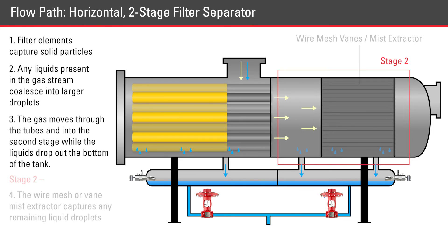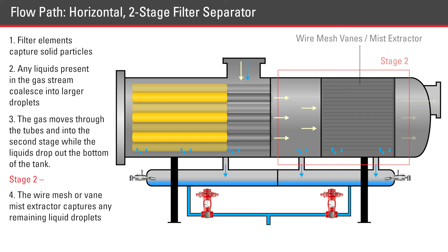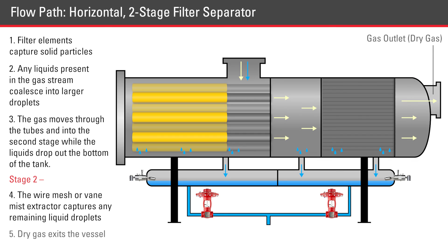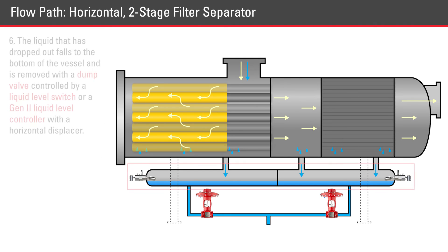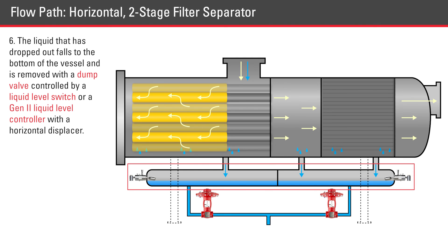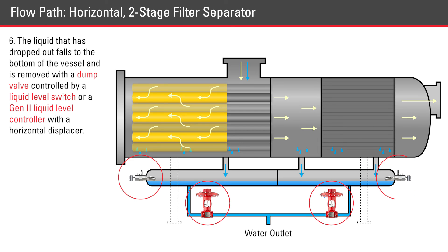In the second stage, the wire mesh vane mist extractor captures any remaining liquid droplets. The resulting gas stream is then virtually free of all particles no larger than the micron filter being used. The liquid that has dropped out falls to the bottom of the vessel and is removed with a dump valve controlled by either a liquid level switch or a Gen2 liquid level controller.